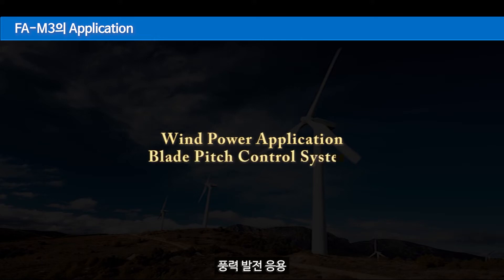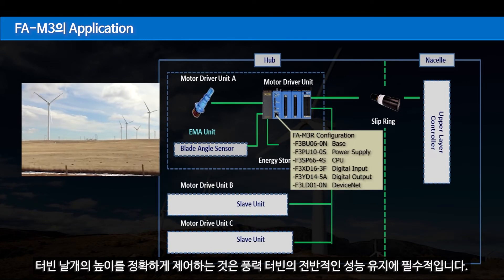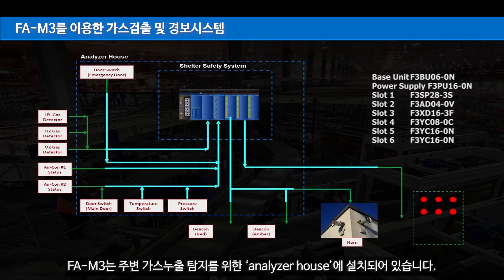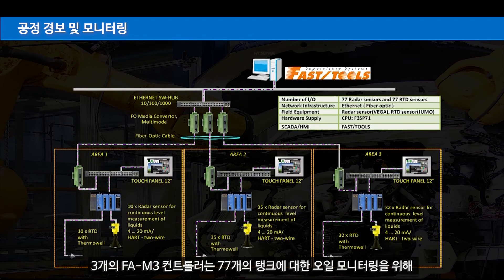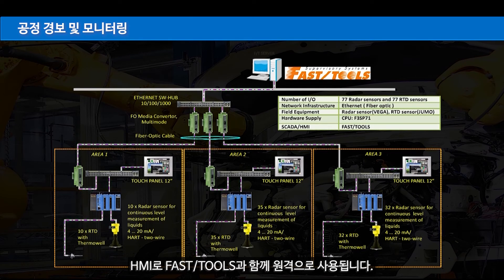FAM3 applications include wind power: a blade pitch control system accurately controls the pitch of a turbine's blades based on rotor position and wind conditions. For gas detection, the FAM3 was installed in an analyzer house to detect gas leaks; once gas is detected, it generates an alarm to alert the operator. For process alarm and monitoring, 3 FAM3 controllers are used remotely with FAST/TOOLS as HMI, connecting 77 radar sensors and 77 temperature transmitters for oil monitoring of 77 tanks.